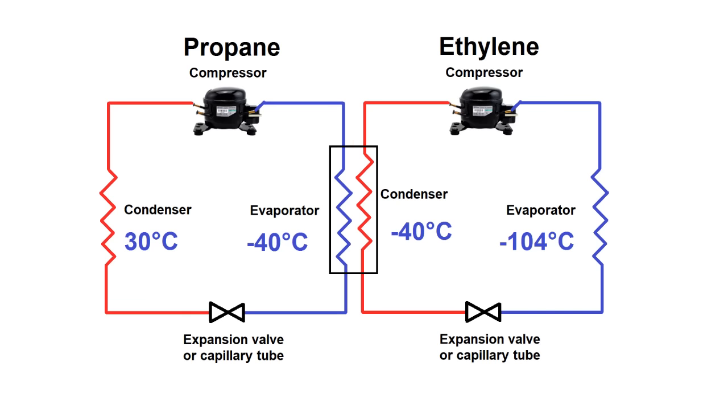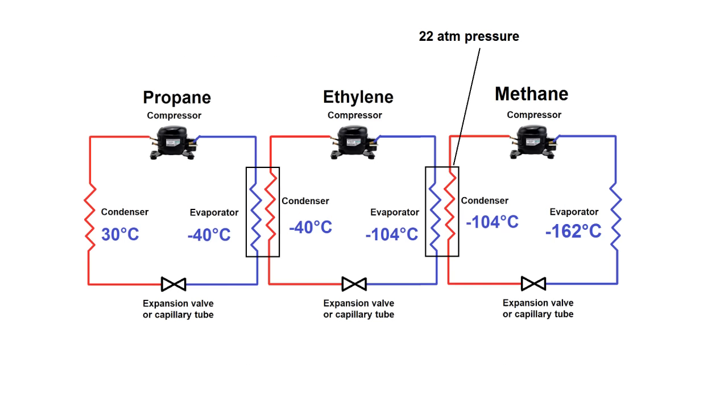At this point, you're probably wondering where do we go from here. Well, theoretically I could build a three-stage device using ethylene in the second stage and methane in the third stage. But if the ethylene evaporator ran at minus 104°C, that would require about 22 atmospheres of pressure for the methane to condense, which would then bring me down to a temperature of minus 162°C if the methane evaporated at one atmosphere. That's a pretty high pressure ratio and a lot of extra complexity.